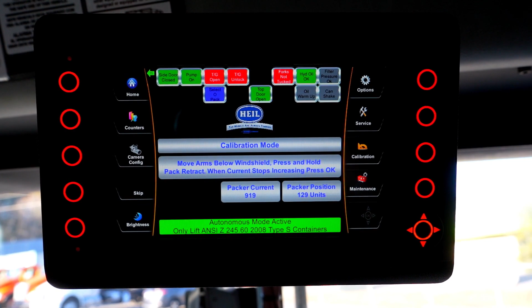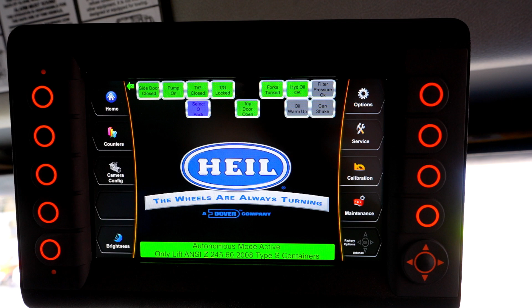Press OK. The next screen you will see will be the home screen. This means you have completed the calibration. Before returning your unit into service, run the dump cycle several times to ensure it works correctly. Recalibration may be needed to correct any undesired movements.